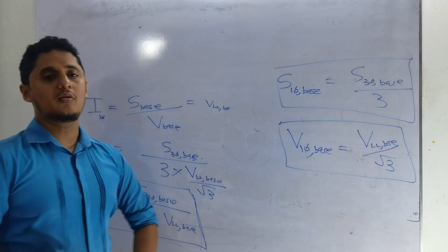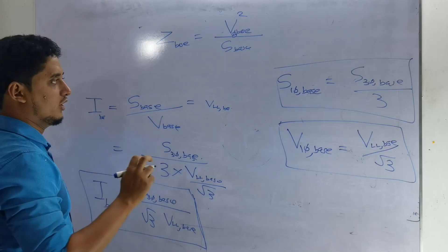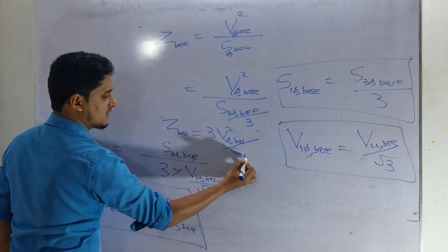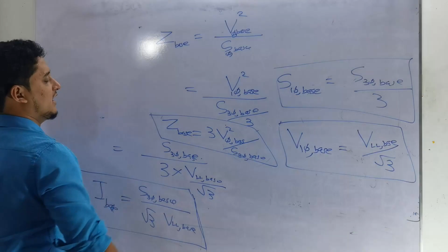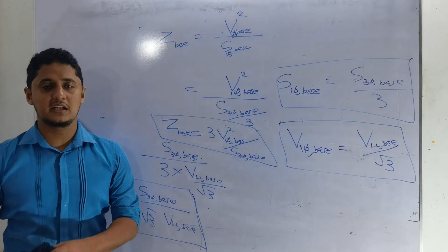Now we will deal with the impedance. Base impedance equals base voltage square divided by base power. For single-phase base voltage and single-phase base power: single-phase base apparent power equals 3-phase base power divided by 3. So from that we can say base impedance equals 3-phase base voltage square divided by 3-phase base power. So this is the equation for base impedance value. These are the equations we are going to deal with for the 3-phase per unit system.